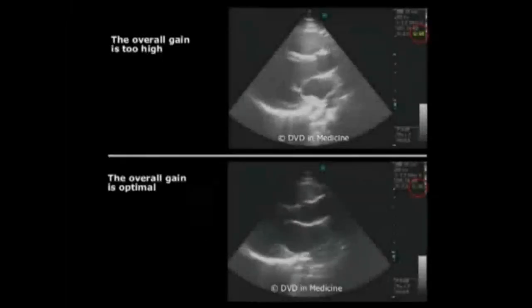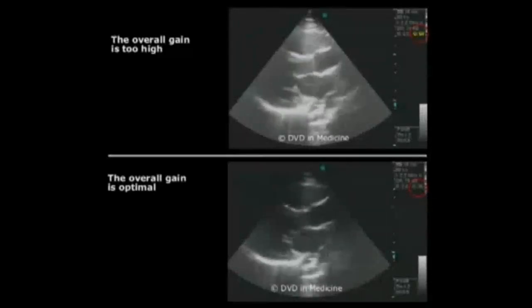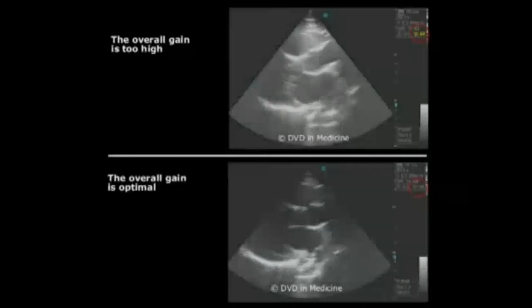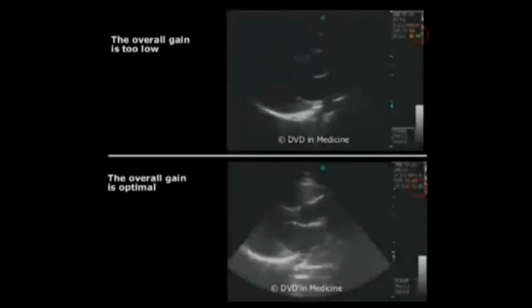Now, on the divided screen, you can see the direct comparison of two real-time images taken from the same patient, an over-enhanced image and an image with optimal level of the overall gain setting. Finally, the image with a very low level of overall gain, and then with an optimal level of the overall gain setting.